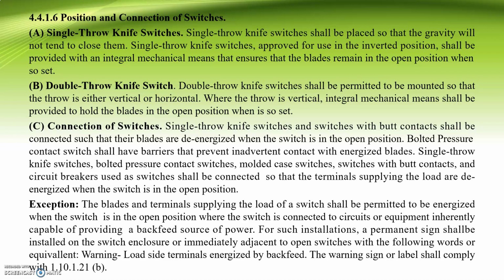B, double throw knife switch. The double throw knife switch shall be permitted to be mounted so that the throw is either vertical or horizontal. Where the throw is vertical, integral mechanical means shall be provided to hold the blades in the open position when so set. C, connection of switches. Single throw knife switches and switches with butt contacts shall be connected such that their blades are de-energized when the switch is in the open position.